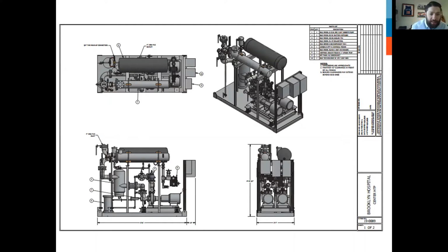And you'll see that trap, like we were just talking about, it's about halfway up. So you got plenty of height to pitch that to your condensate pump. So all you got to do is pitch that to your condensate pump, bring in your steam up top, and pipe out your hot water, and you're done, guys. You're done. And this thing's packed nice and tight. You can fit this in any boiler room. It's a ton of equipment on top of each other as long as you have the height. This is a beautiful layout.